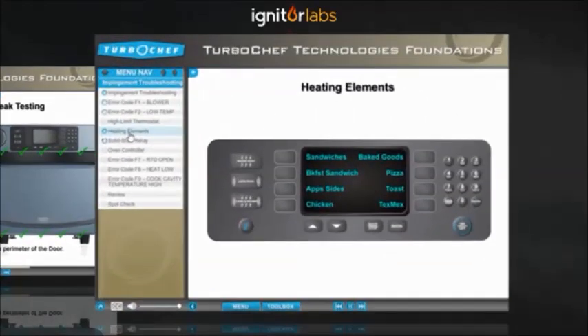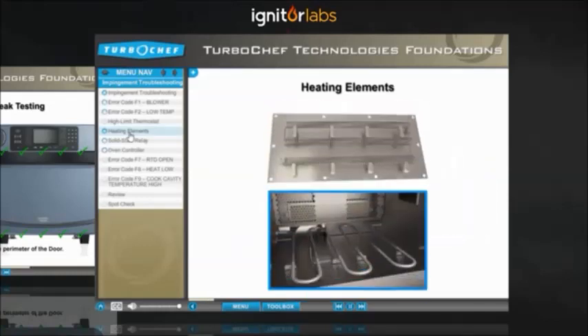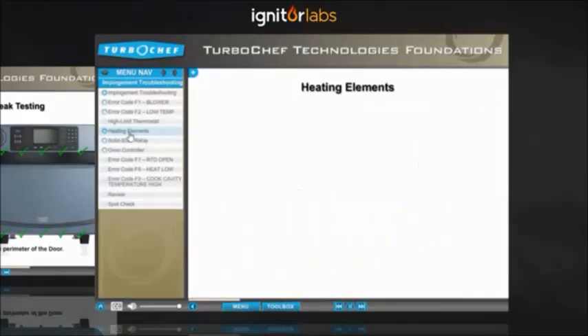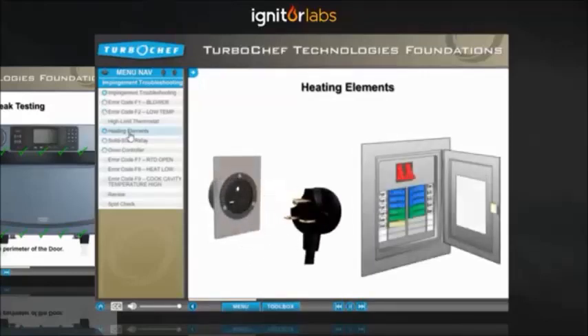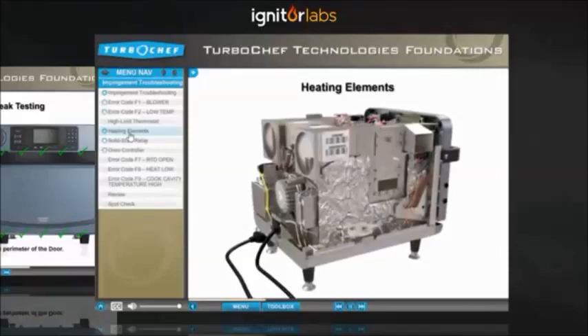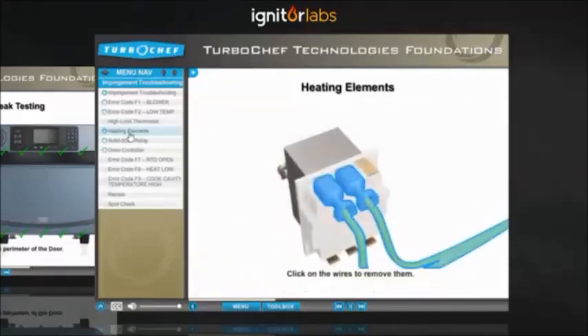A faulty heating element can also trigger an F2 or an F8 error code. If an element is faulty, the oven won't be able to maintain its temperature. To determine if an element is faulty, first make sure the oven is disconnected from the power supply. Disconnect these wires from the high limit thermostat. Just click on them.